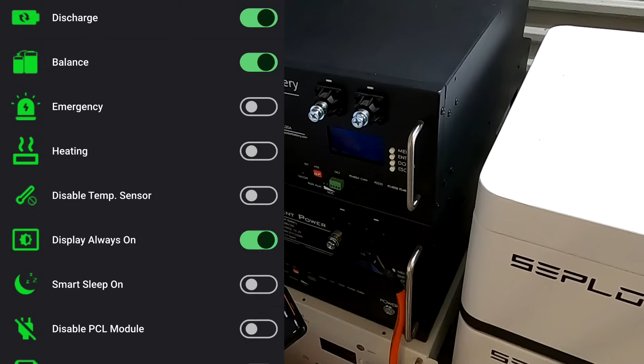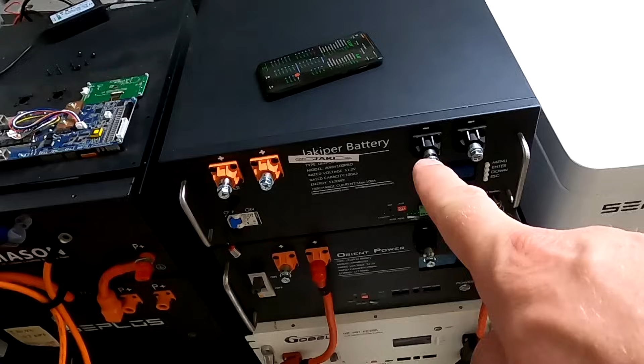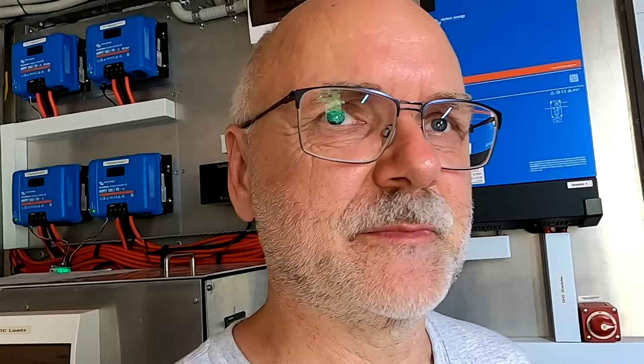But honestly, I don't think we need to set up anything in this BMS here, because this will be only the slave, and the master battery will be connected to our JK BMS. So master, slave. But you want to make sure everything is correctly set up, just in case the communication breaks between the two BMSs and the master cannot monitor the situation of the slave battery anymore. So you still want to set up the charging logic in the slave BMS as well. We'll dive into all this in the next video, when we actually connect these two batteries in parallel and see how they work.